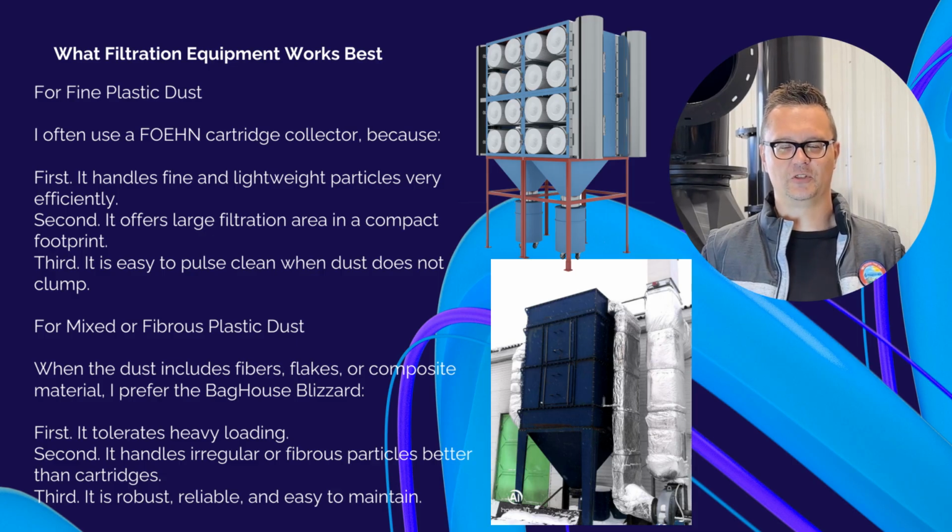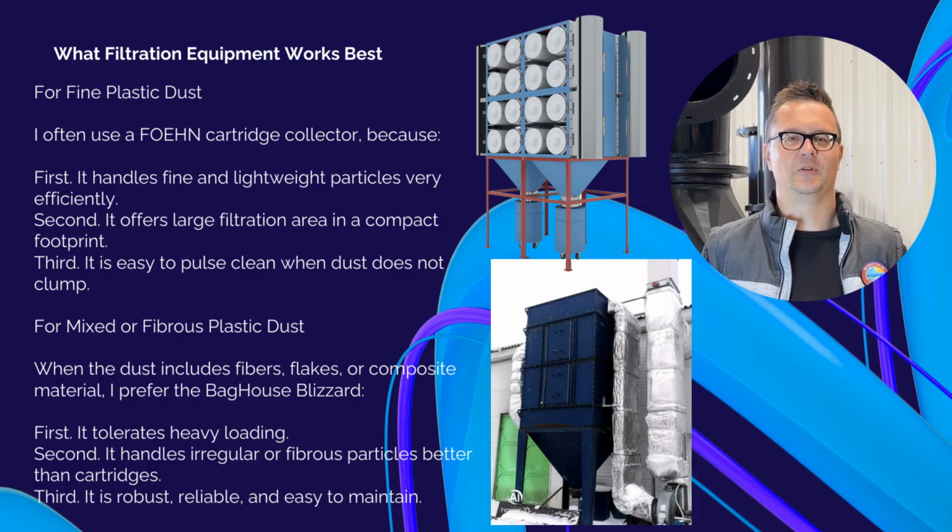For mixed or fibrous plastic dust, when the dust includes fibers, flakes, or composite material, I prefer the Baghouse Blizzard. First, it tolerates heavy loading. Second, it handles irregular or fibrous particles better than cartridges. Third, it is robust, reliable, and easy to maintain.